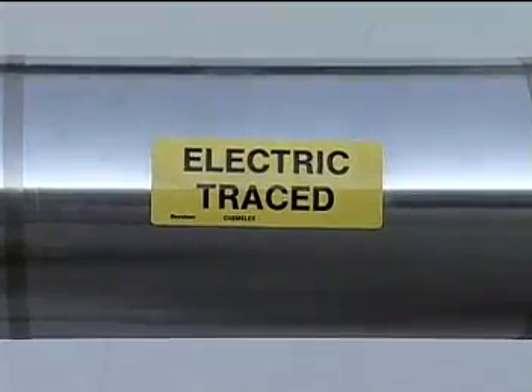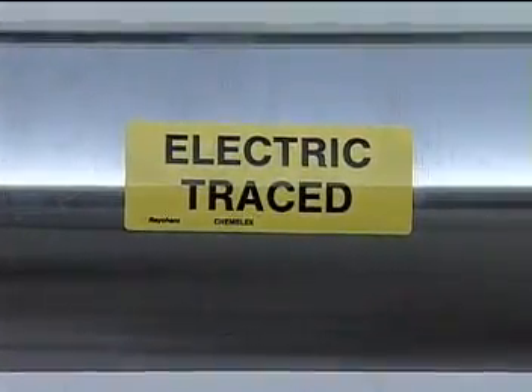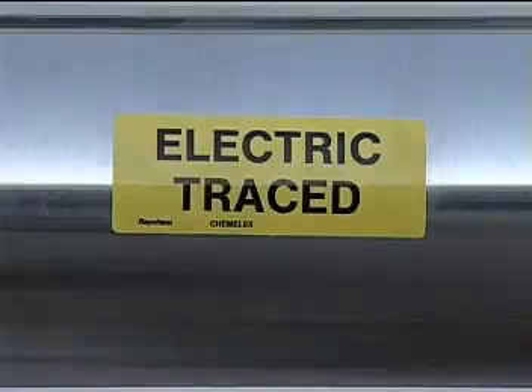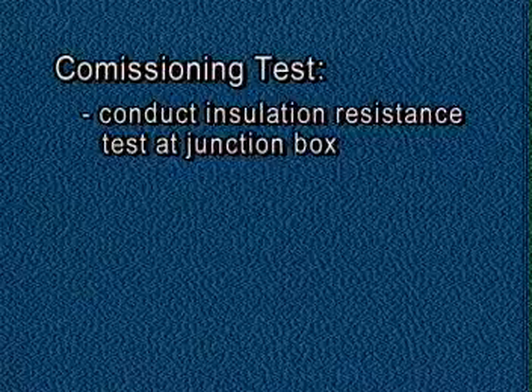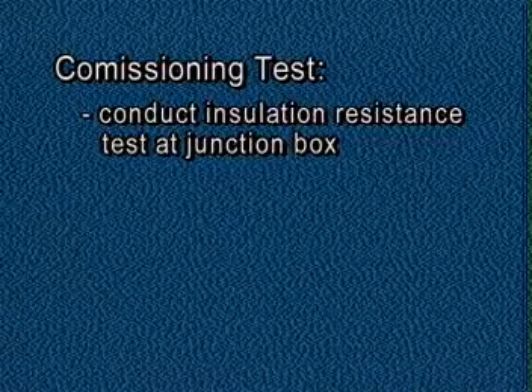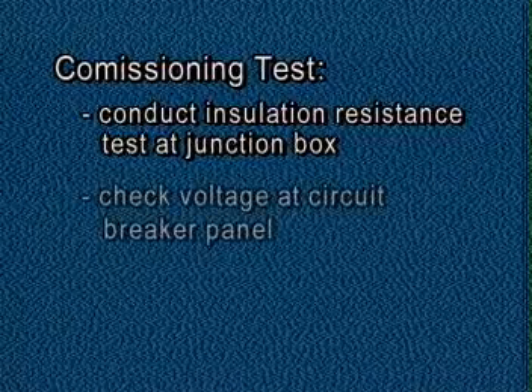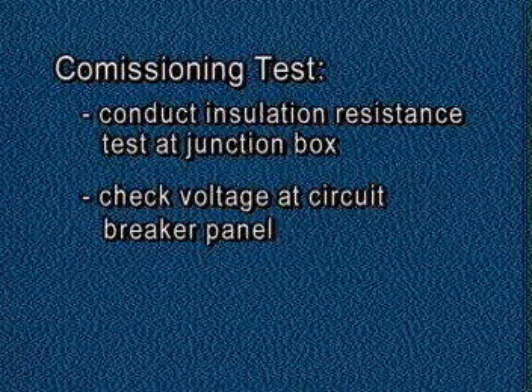Also be sure to label the locations of all connections such as T's, splices, and end seals. When all the components, insulation, cladding, and labeling are installed, the system is ready for a commissioning test. To perform this test, first, conduct the insulation resistance test of the system at the junction box. Then, check voltage at the circuit breaker panel.